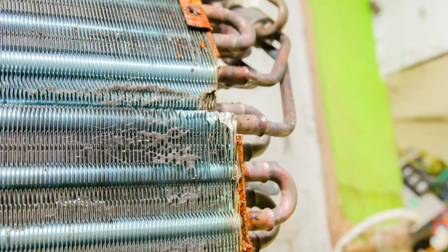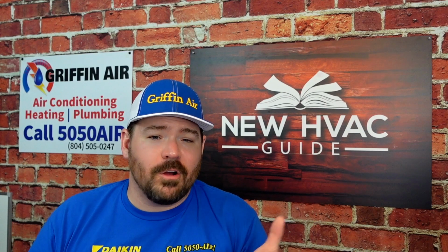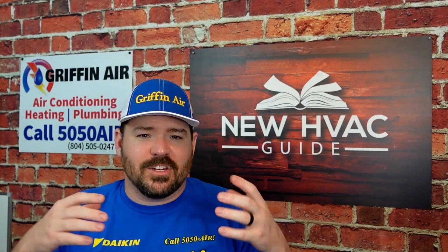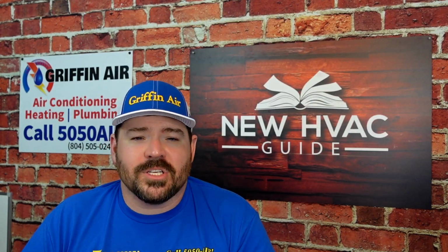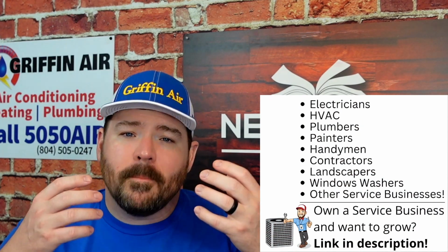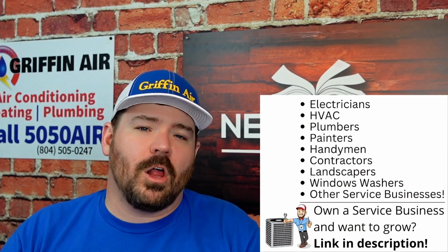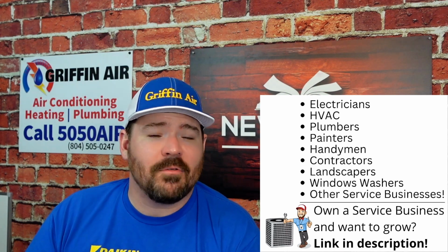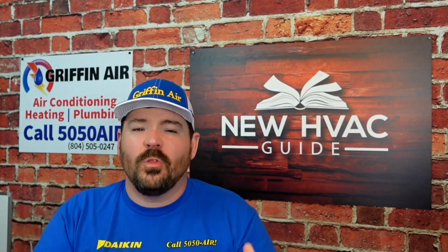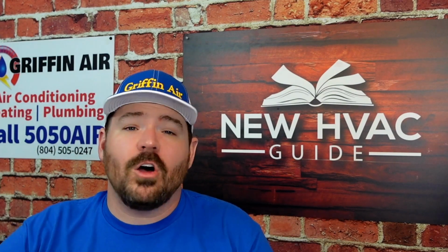Number four, something's dirty. A dirty air filter, or a dirty evaporator coil, a dirty fan wheel, dirty ductwork, right? We already talked about duct issues, but all these things, if they get dirty, especially like that fan wheel, for example, if the dirt's not properly balanced on that fan wheel, it can cause it to vibrate more than it normally would. Any sort of airflow issues with that system or something needing to be maintained better can also cause vibrations. We've had customers that we went out and did a proper maintenance, tune-up, cleaning, whatever you want to call it, have actually called us back and said, wow, I can't remember a time that my system has run this quiet. Things getting dirty in there and air having to be pulled through areas or just things starving for air can cause vibrations in that system.